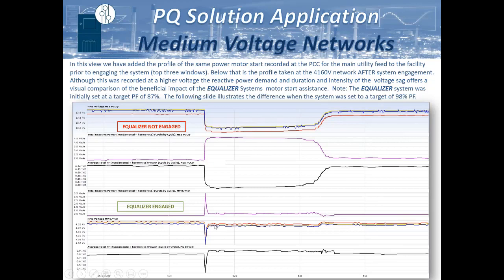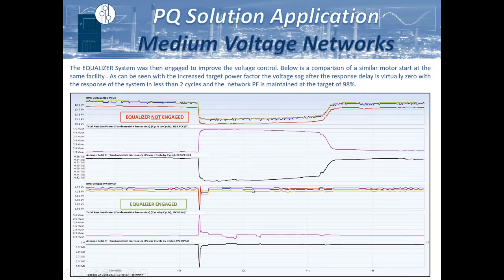And you can see that we're maintaining this voltage level at a very high tolerance. This sag is less than two cycles long, which is the maximum time required for the system for a full load demand response. When we set it at 98%, it had an even greater voltage stability. This allows the opportunity to adjust your taps and step things back down so that they operate where the equipment was designed for. Minimizing the current and optimizing the voltage levels allows for much less heat being generated on the network, as well as fewer harmonics, which can extend equipment asset life quite significantly. This has a particular impact on VFDs on our network.